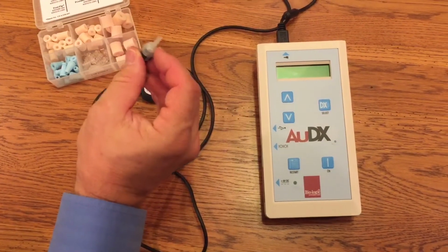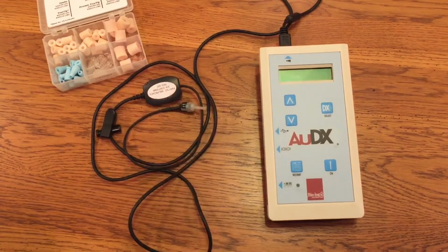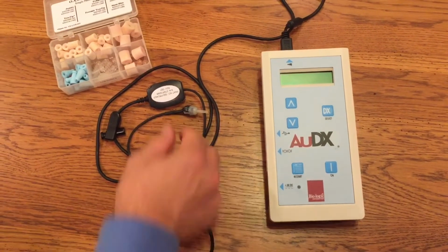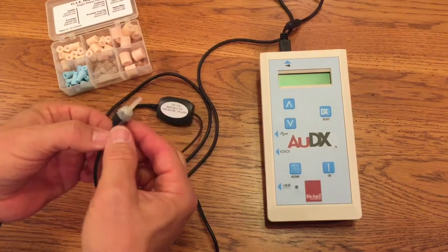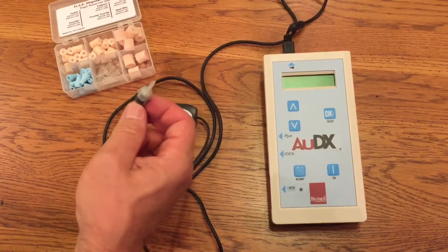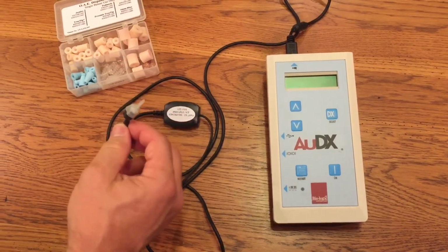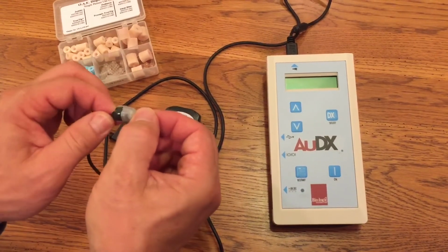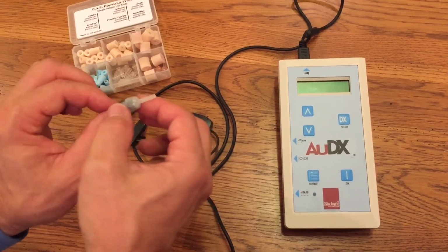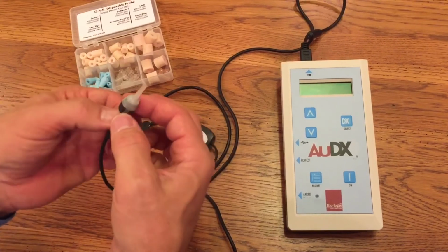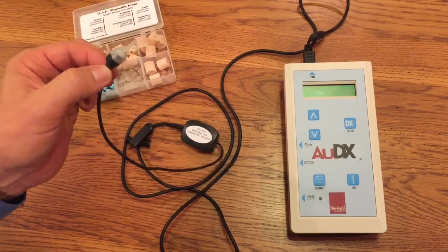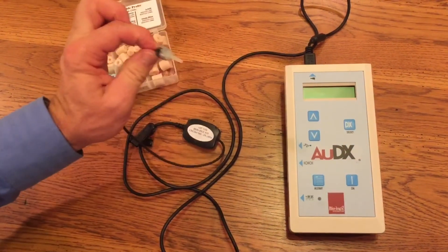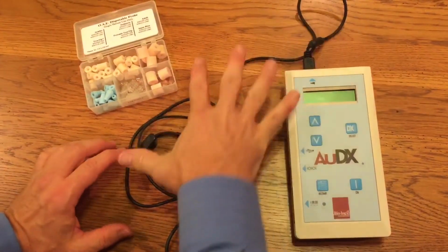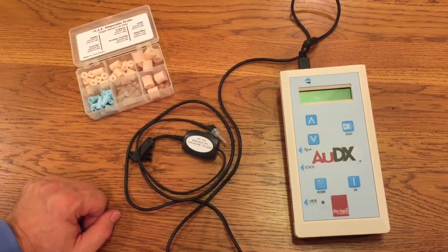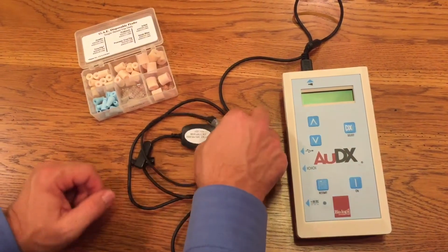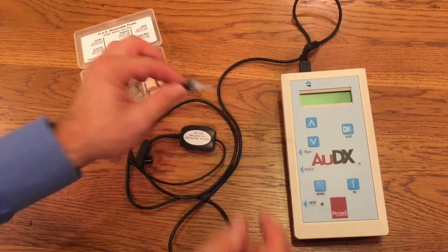nozzles and tips again need to be replaced when they become clogged. And don't attempt to clean the probe itself. We don't want to get any moisture in there. It's easier, these are disposable, and it's better to just replace one than it is to try and clean this assembly and risk damaging it by getting moisture into the unit. These probe assemblies here are almost $500, about $475, whereas the nozzle here is under $1.